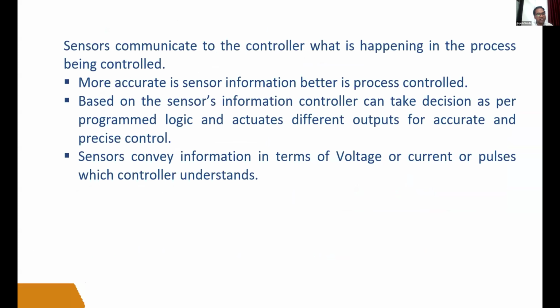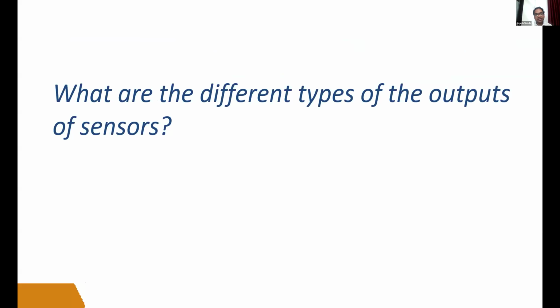So what is the function of the sensor? The sensor communicates to the controller what is happening in the process being controlled. The more accurate the sensor information, the better the process is controlled. Based on the sensor information, the controller can take the decision as per the programmed logic and actuate the different outputs for accurate and precise control. Sensors convey the information in terms of voltage or current or pulses, which the controller easily understands.